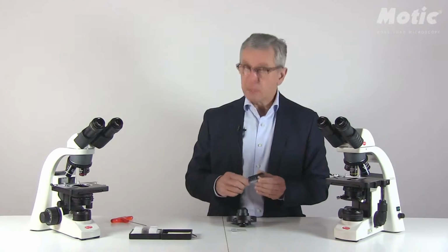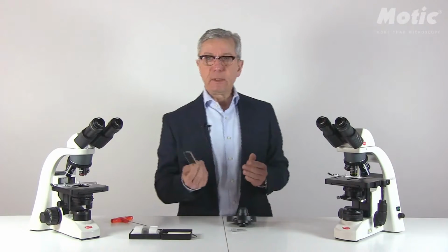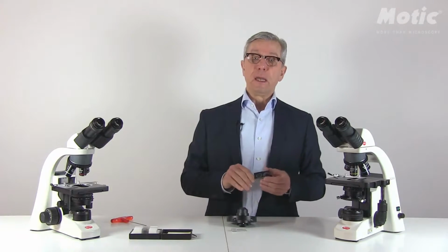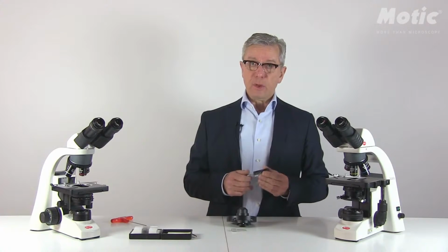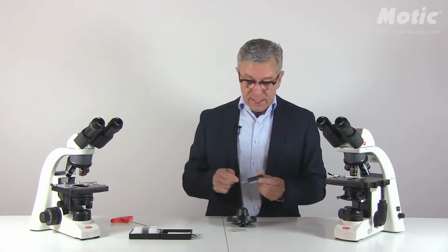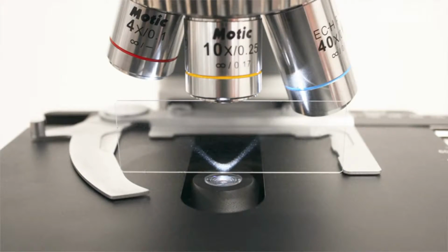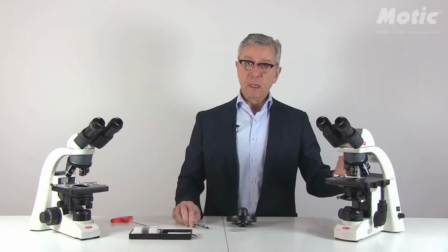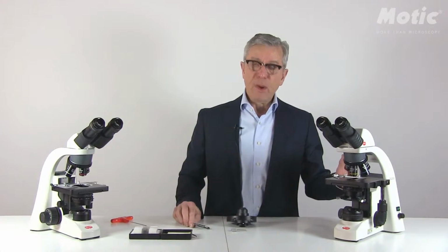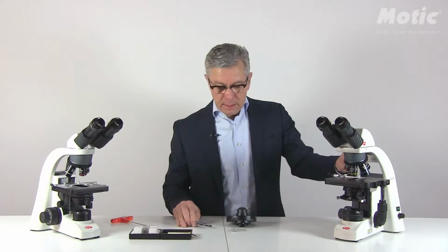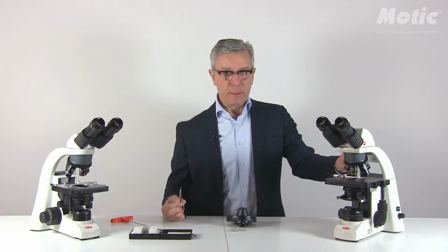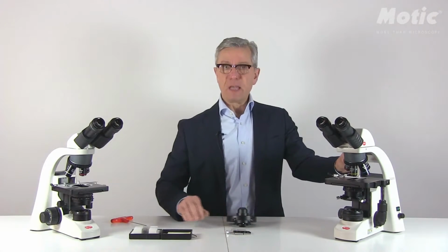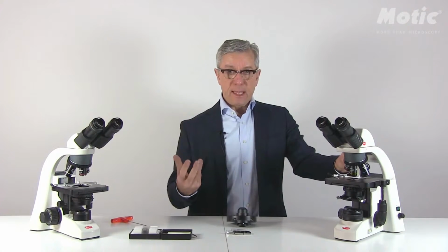This central stop is a simple piece of metal which is mounted here in a slider, in this case in a turret solution, and it is going to eliminate all the direct light which passes the sample and will go to the microscope. Only the light that passes this ring-shaped slot will enter the sample. But thanks to the condenser optics, it will miss the front lens of the microscope. So at the end, we will have a dark background, similar to the polarization contrast, but of course on a completely different setup.